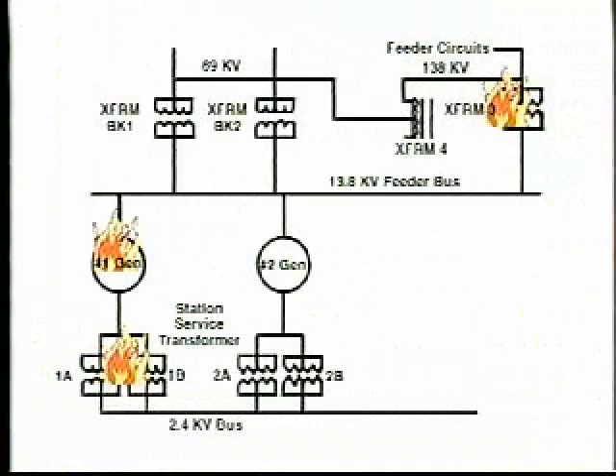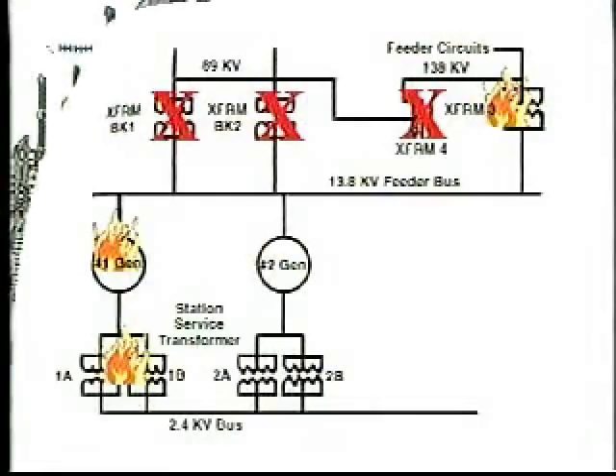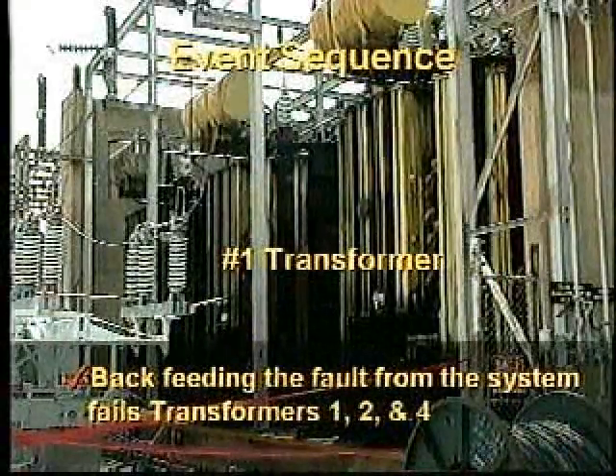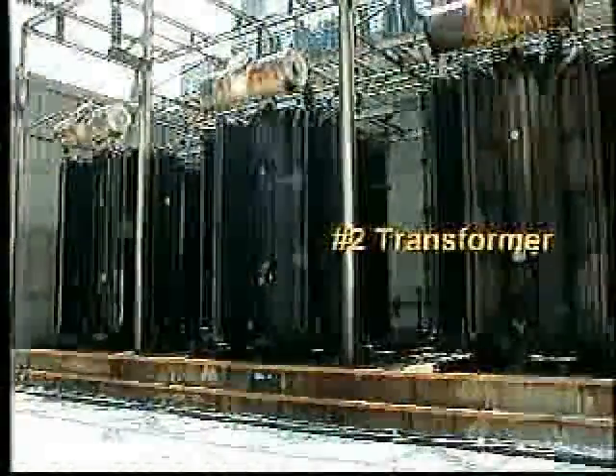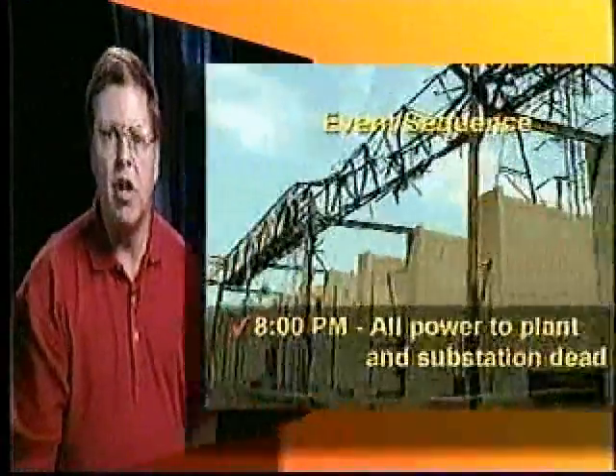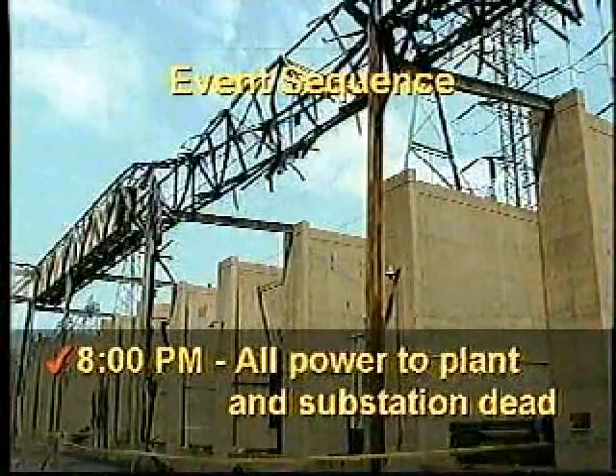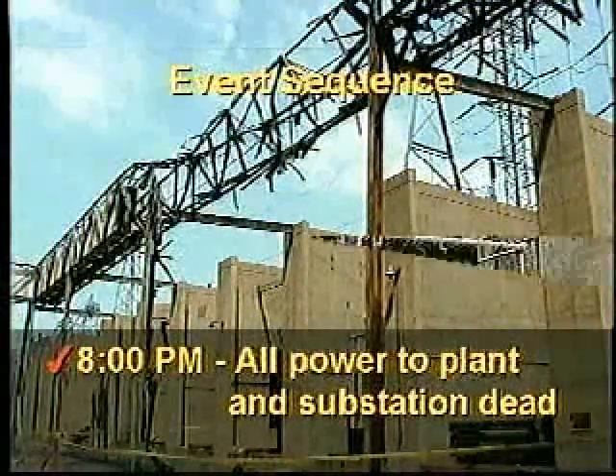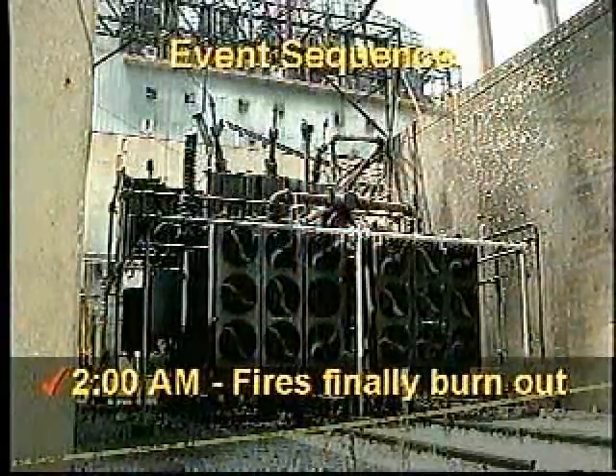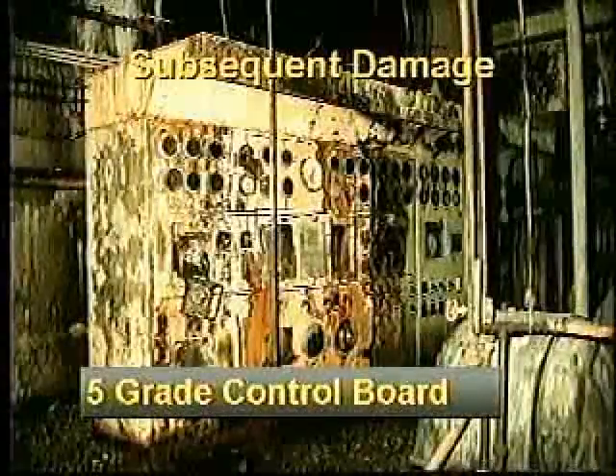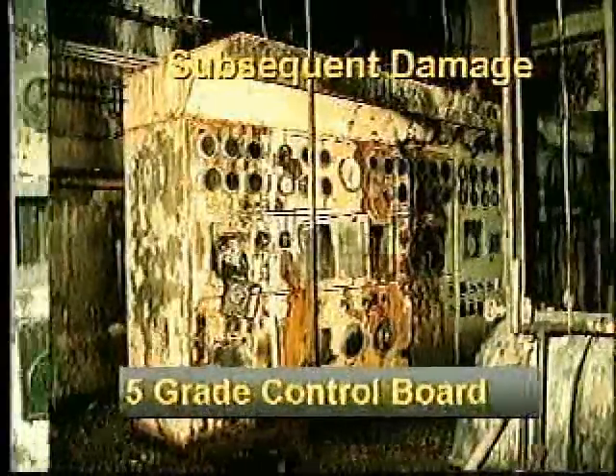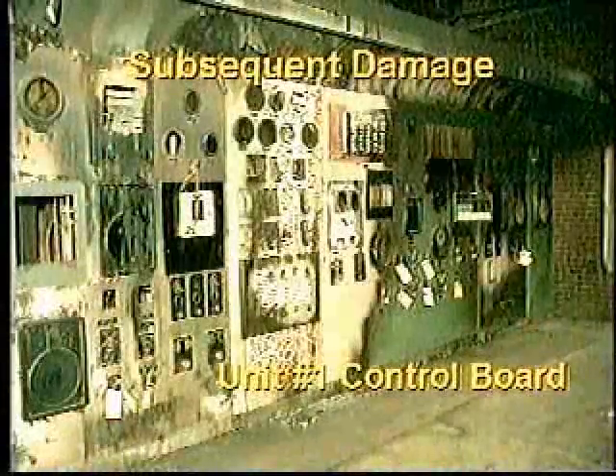Looking at our electrical one line again, as the fire progressed and the electrical fault continued, transformer bank number 1 and number 2 were next to fault, followed by transformer number 4. Backfeeding the fault from the system fails transformers 1, 2, and 4. At 8 p.m., all power to the plant and the substation is finally dead. In this picture, we see the electrical bus duct, which was burning with the 3-phase fault, giving the bright star look of an earlier picture. At 2 a.m. in the morning, the fires are finally burned out. Subsequent damage includes this panel, which is located underneath Unit 1's turbine generator. Additional damage includes Unit 1's boiler control board.